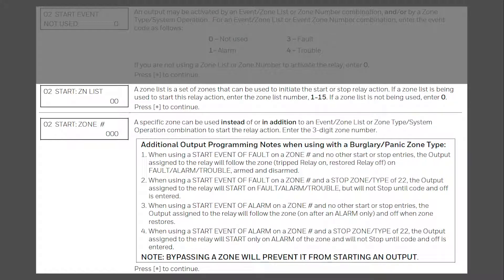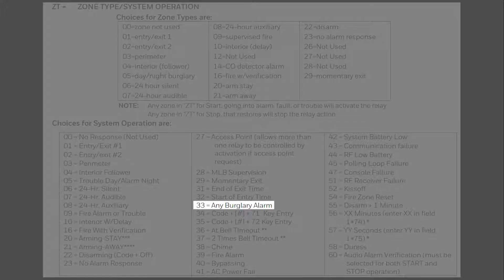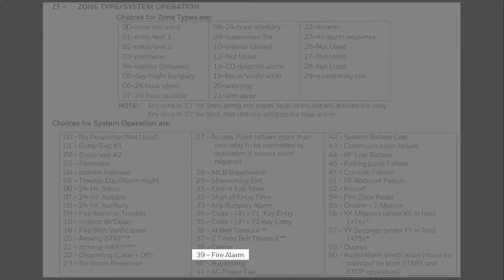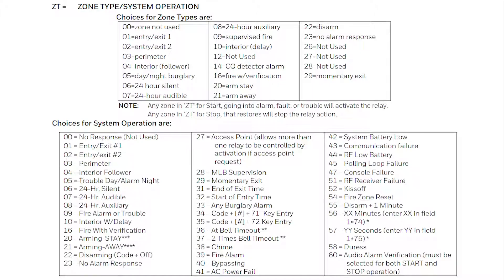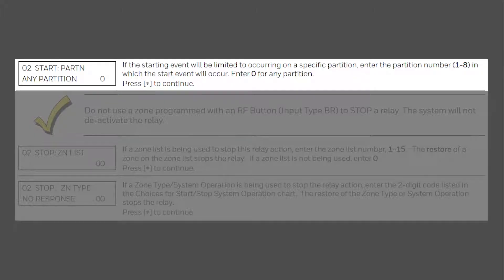The next three prompts will allow us to select our start zone list, start zone number, or start zone type. For a zone number, simply enter in the 3-digit zone number. For zone list, enter the 2-digit zone list. And for zone type, enter the 2-digit zone type that can be referenced from this list, such as zone type 33 which is any burg alarm, and zone type 39 which is any fire alarm. You can have your start action be any combination of zone list, zone number, and zone type. Press star to move forward once you've made your selection. Enter the partition that this action needs to originate from, then press star.